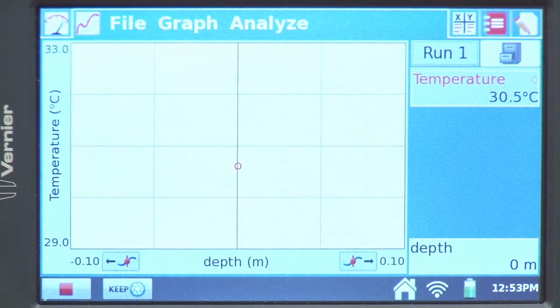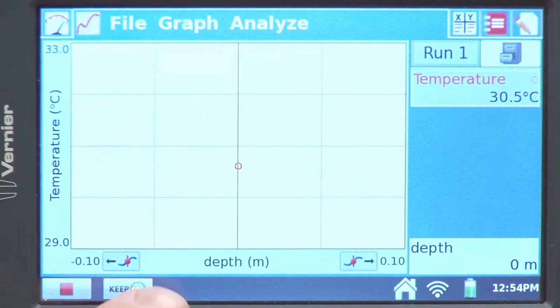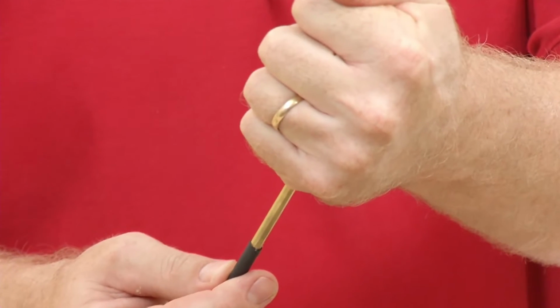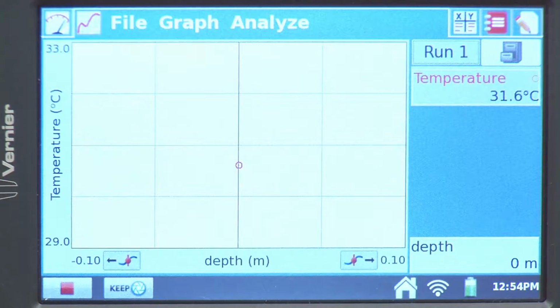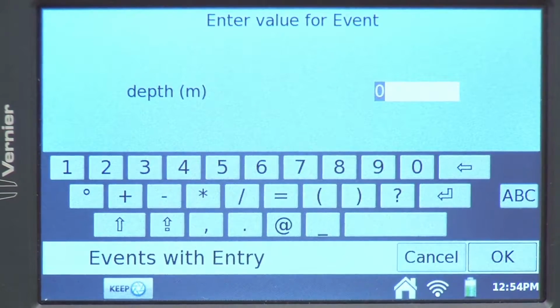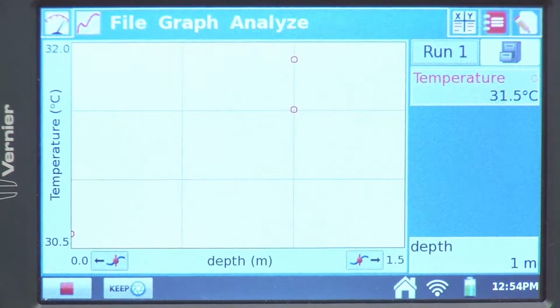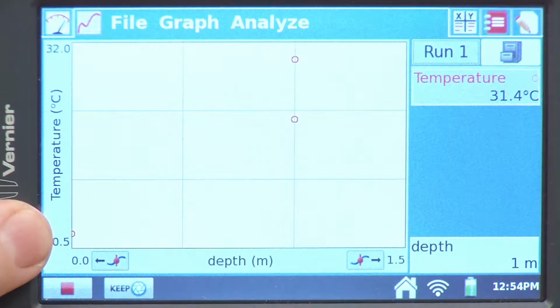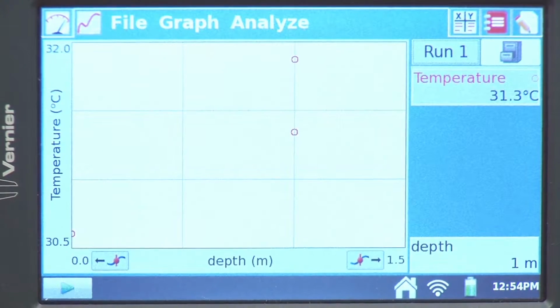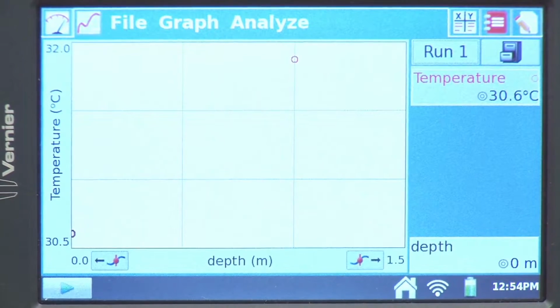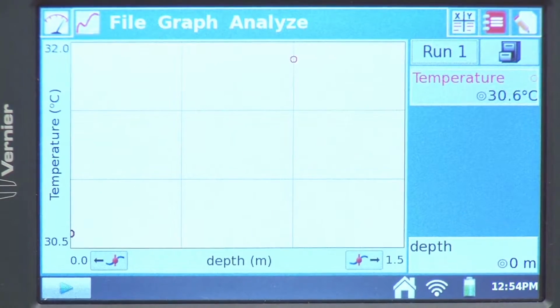Say OK. And now I might say, well, let's say I do put it into the water here, and I'll just hold it in my hand to make the temperature change a little bit. And then I hit keep. And maybe now I say, instead of at 0, now it's at 1 meter, and I say OK. And now I've got my second reading. So I've got a reading here and a reading over there. If I hit stop, then we see the reading here and the reading there for those two different depths in this case. And so what we'll do out in the field is I actually will collect the data looking at different depths, and then we can take a look at our data out in the field.